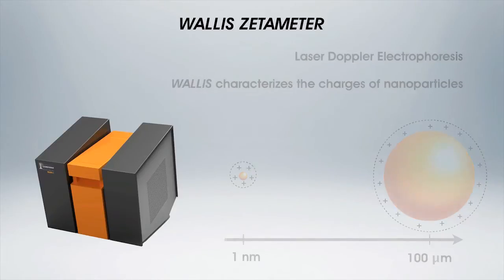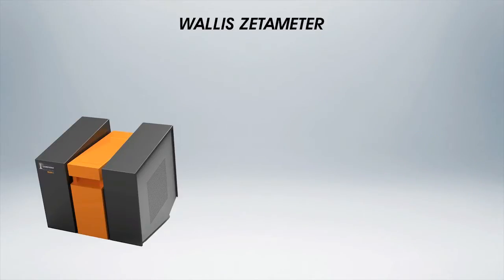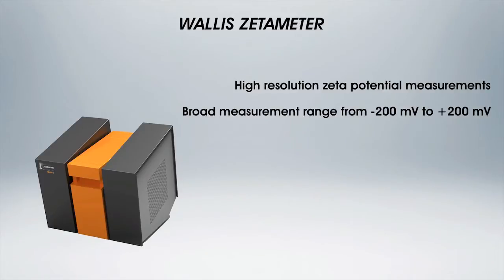Its signal acquisition chain, without correlator, is specially optimized for high-resolution zeta potential measurements while preserving a broad measurement range. Indeed, Wallis can measure zeta potential from minus 200 millivolts to plus 200 millivolts with an unequaled 0.1 millivolt resolution.